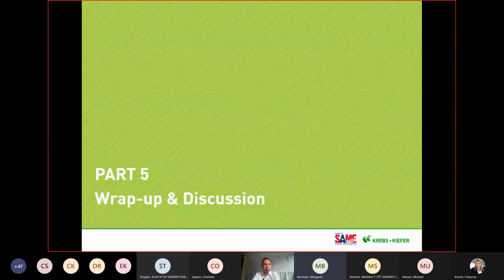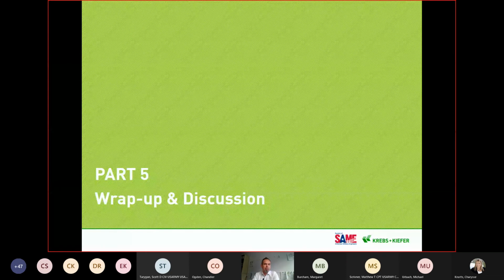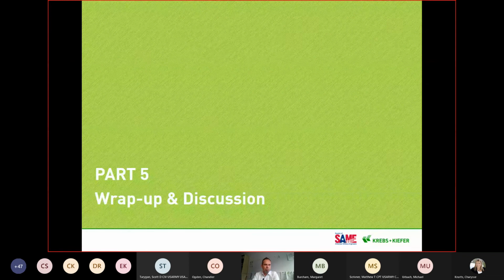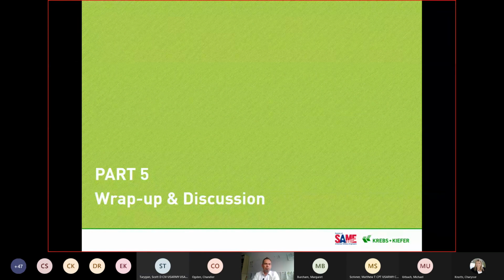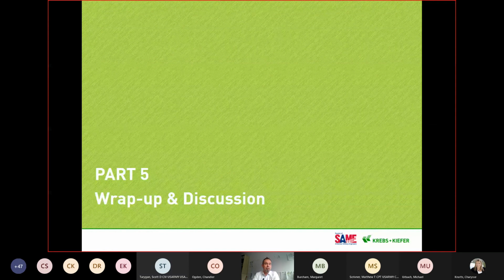One word on sprinkler systems: don't let anybody, especially the German AHJs, tell you it's a base requirement to build sprinkler systems to German or European standards. All the national codes and laws say that if you put in a sprinkler system, it has to be safe and appropriate to use. It doesn't say you're only allowed to use German or European standards. I know a lot of non-US military projects in Germany, especially storage and storage handling, that are protected by FM sprinkler systems or NFPA 13 sprinkler systems.